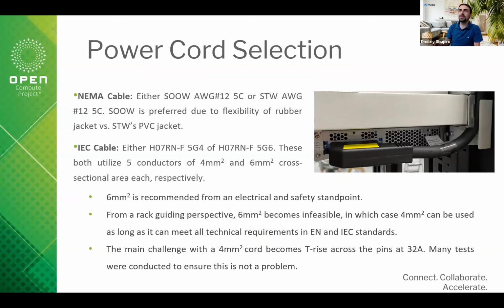For the IEC cable, it's an H07 RN-F 5G4 or 5G6 standard. Six millimeters squared cross section per wire is recommended from an electrical and safety standpoint because it can handle higher currents. But when you try to route that 6mm square cable through the rack, it becomes very, very difficult, pretty much impossible. That's why we went to the 4mm squared.